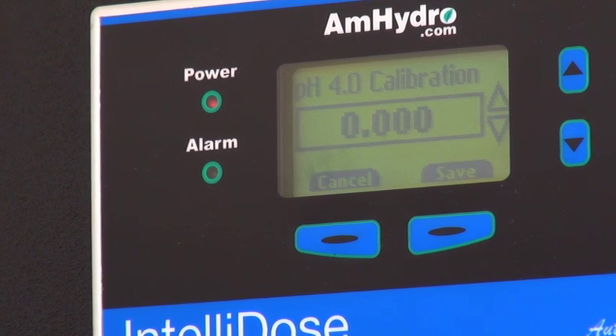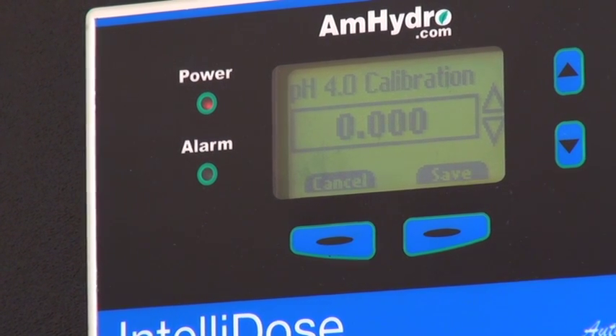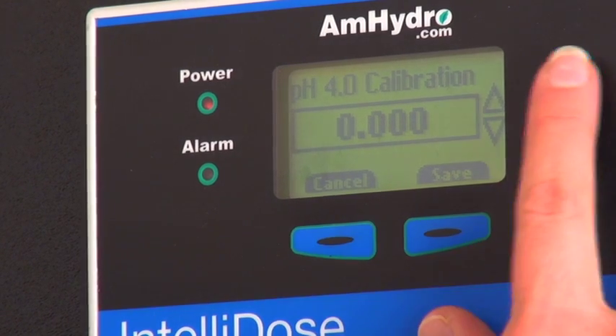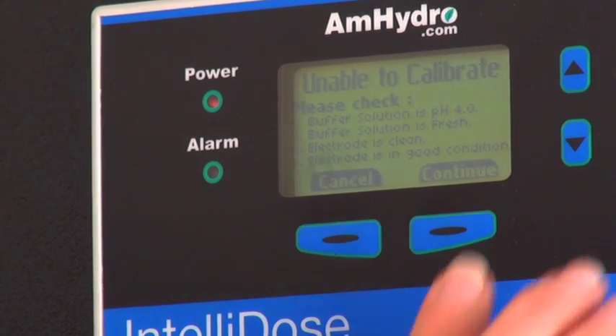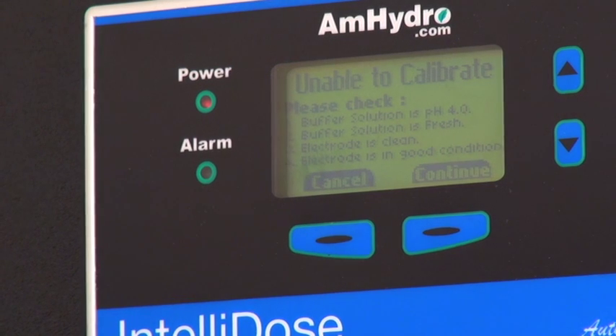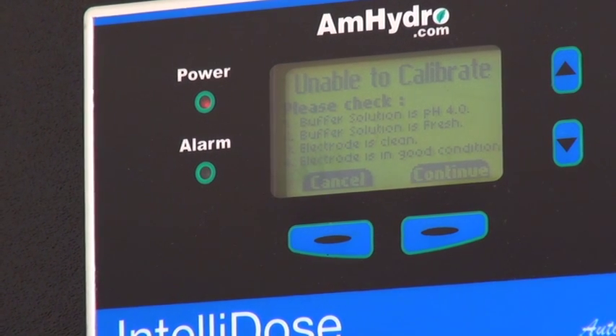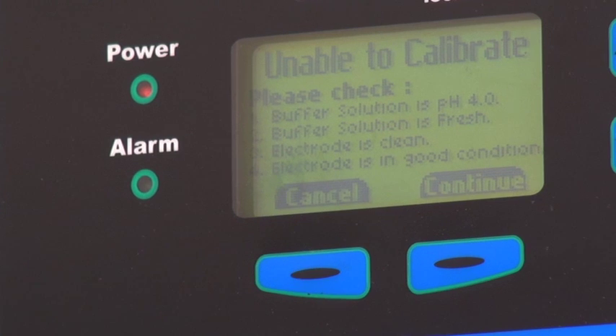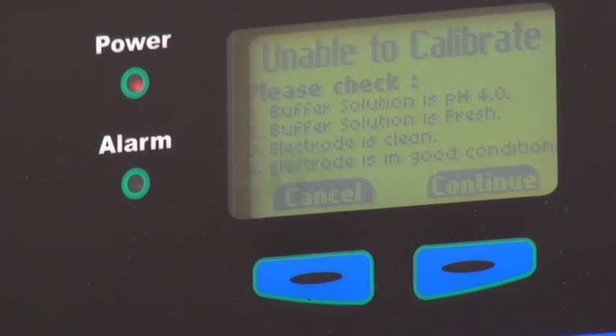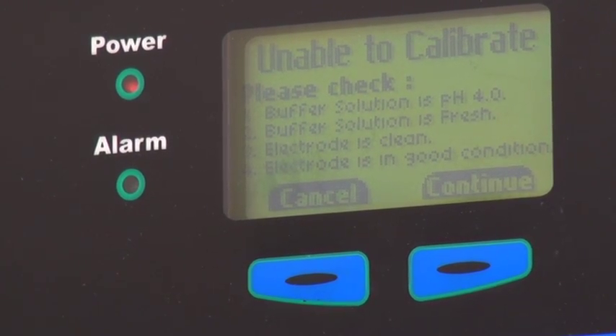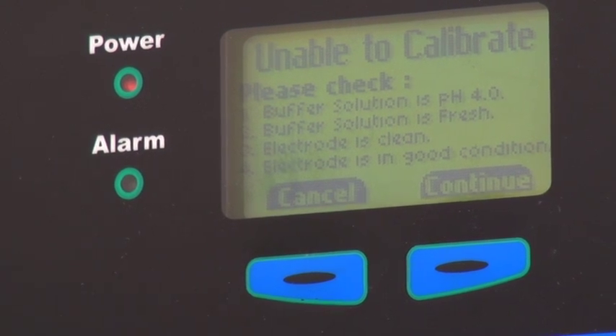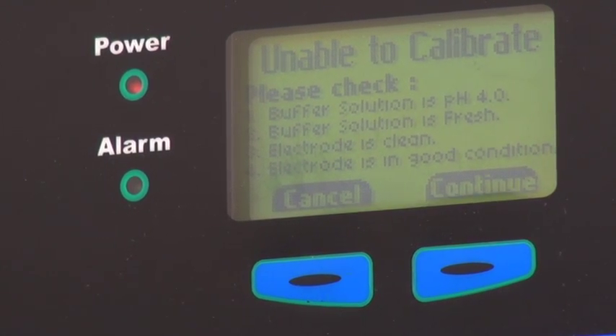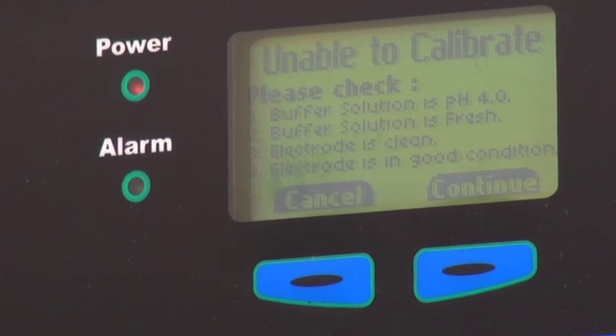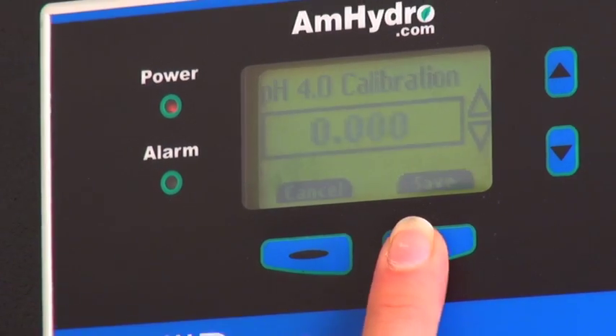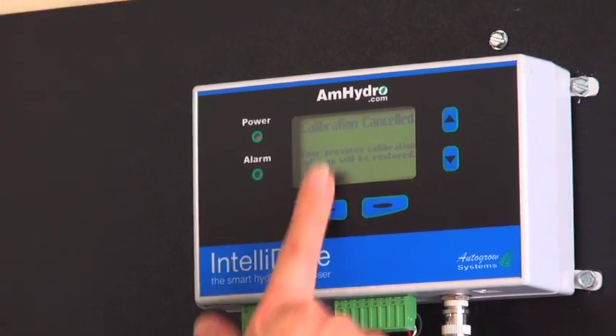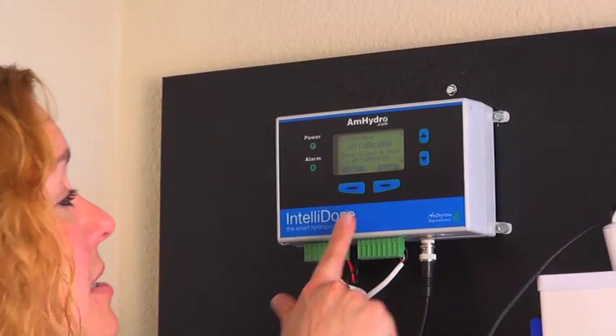If you put it into the wrong solution, so you leave it in the 7.0 solution, or it's just in plain water, it'll realize that you can't actually calibrate to 4.0 and that the solution is wrong. So if you try and calibrate it, it'll tell you, please check that the buffer solution is pH 4.0, that the solution is fresh, that the electrode is clean, and that the electrode is in good condition. So if you accidentally put it into the wrong solution to calibrate it, the unit will know, won't allow you to calibrate it, and will remind you to put a couple checkpoints in to make sure you've got it set right. And then it'll cancel your calibration until you get the right solution.